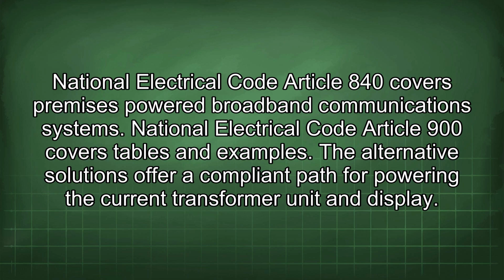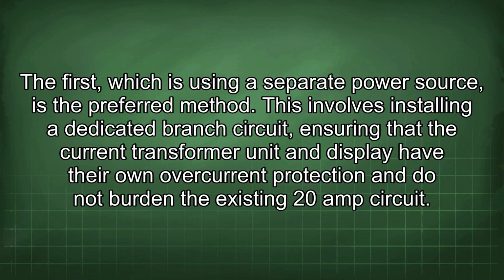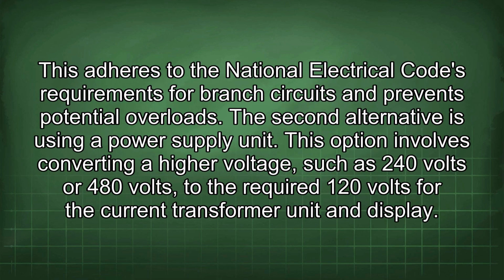The alternative solutions offer a compliant path for powering the current transformer unit and display. The first, which is using a separate power source, is the preferred method. This involves installing a dedicated branch circuit, ensuring that the current transformer unit and display have their own overcurrent protection and do not burden the existing 20 amp circuit. This adheres to the National Electrical Code's requirements for branch circuits and prevents potential overloads.